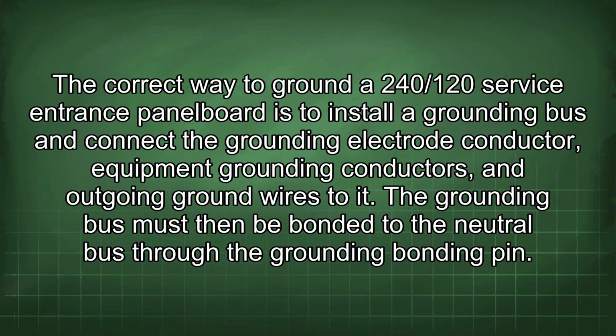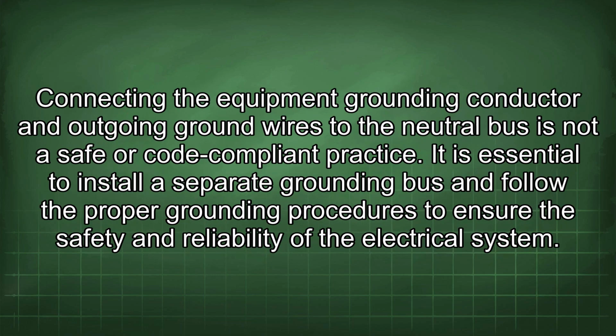The correct way to ground a 240/120 service entrance panel board is to install a grounding bus and connect the grounding electrode conductor, equipment grounding conductors, and outgoing ground wires to it. The grounding bus must then be bonded to the neutral bus through the grounding bonding pin. Connecting the equipment grounding conductor and outgoing ground wires to the neutral bus is not a safe or code-compliant practice. It is essential to install a separate grounding bus and follow the proper grounding procedures to ensure the safety and reliability of the electrical system.